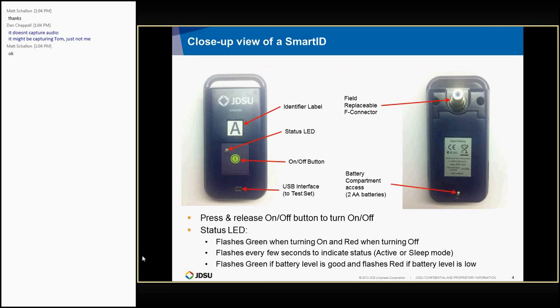So for somebody that's never seen a Smartid, this is what it looks like, front and back. There's not too much to point out. The identifier label is just a press-on label. It can be anything from A to Z. You just have to match it up with whatever you register the probe as when you register probes on the meter. We'll get to that a little later.